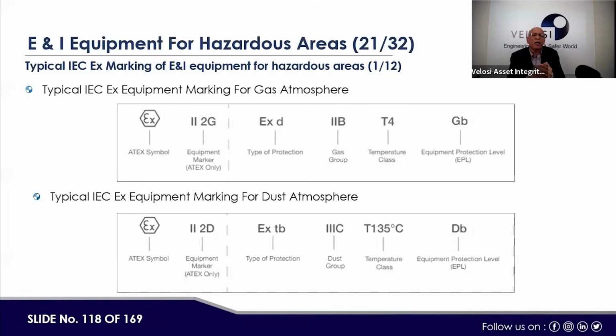And there is also one more piece of work, and a lot of inquiries are coming nowadays: third parties, inspection companies or engineers are asked to come and survey our facilities and make sure all our electrical and instrumentation installations in the process area match the applicable HAC drawing. First of all, the HAC drawings must be up to date. Number two, look at the equipment. It means we need to look at the equipment schedule or list of equipment, and see in which zone which equipment is installed, and whether it meets the applicable requirements indicated in this table.